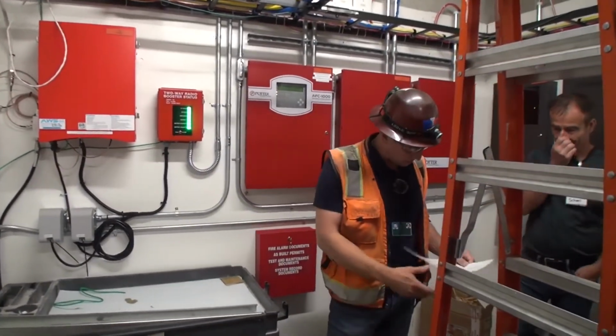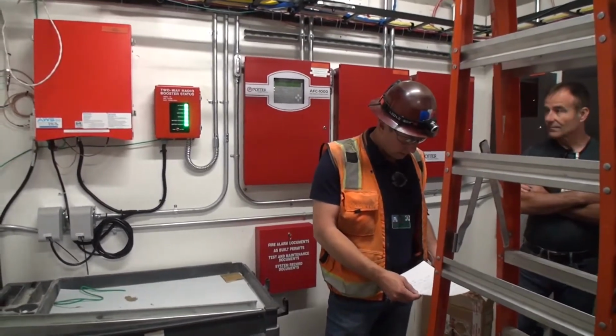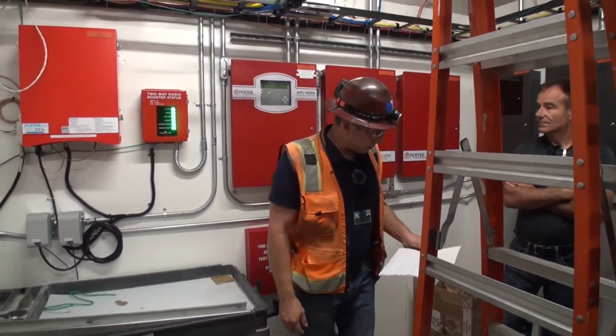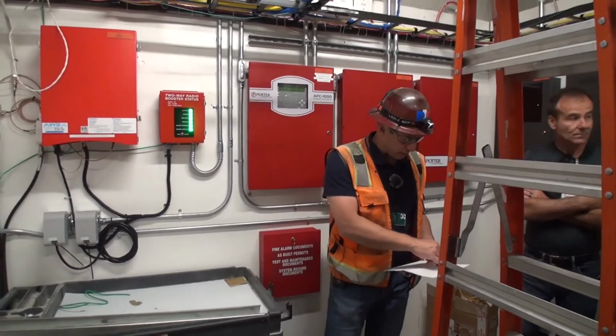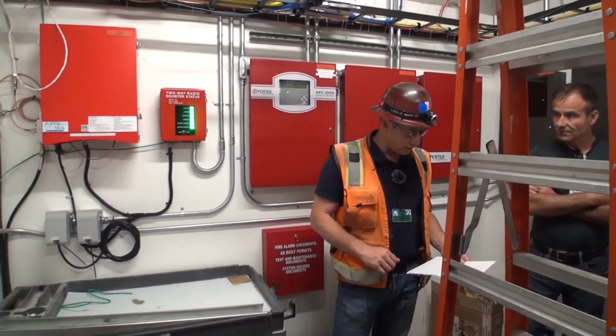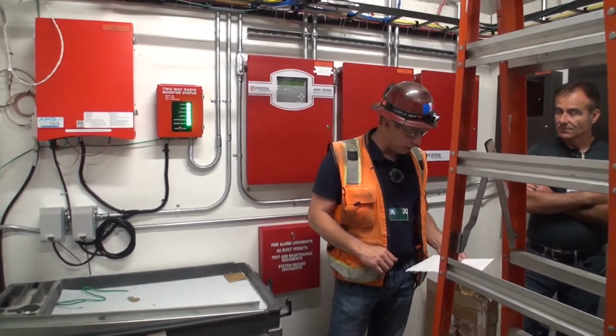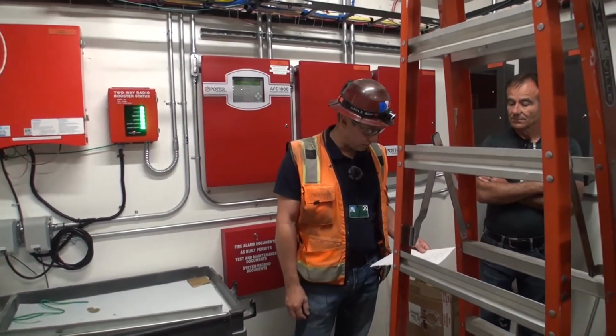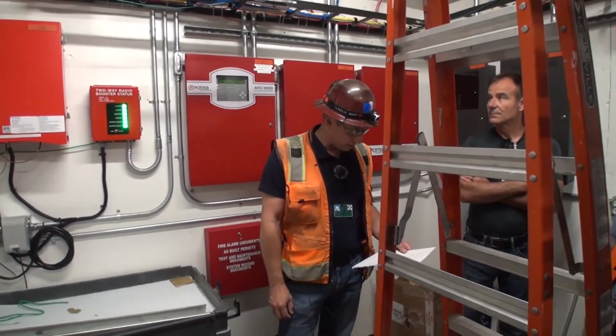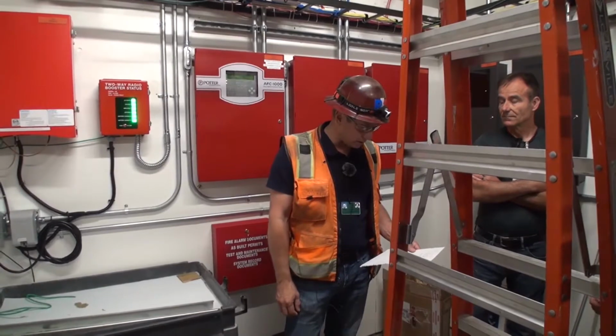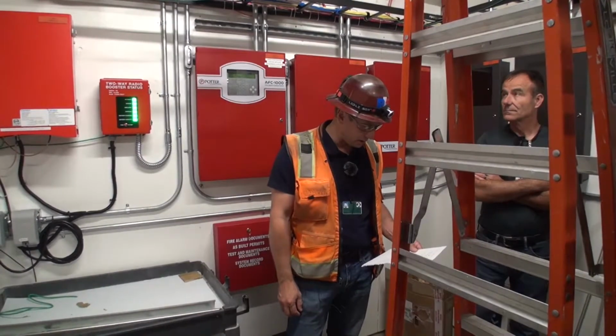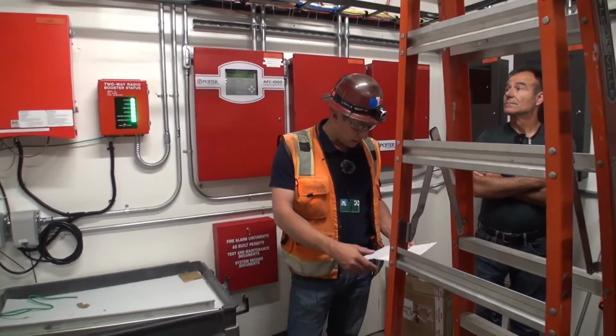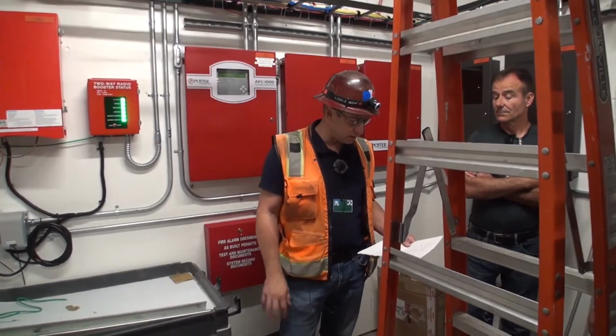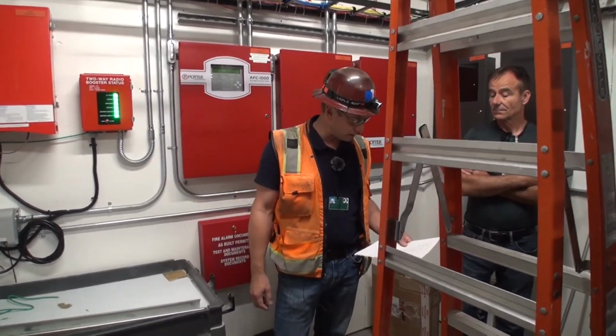She left me some notes here. I'll read this just in case there was something I missed: it provides signal in the building for emergency rescue, fire, and police radios, it's just a booster for them. Annual inspection per fire code is required. It's a physical inspection of the cable, the roof antenna, and the booster panel. There's also an operational inspection, so they'll actually cycle it and make sure it works.